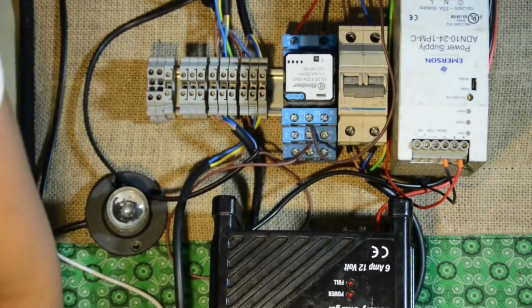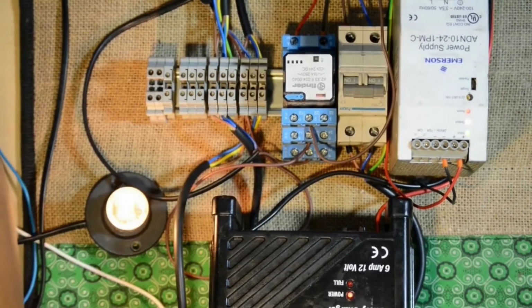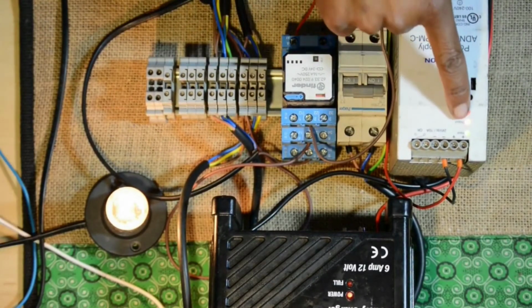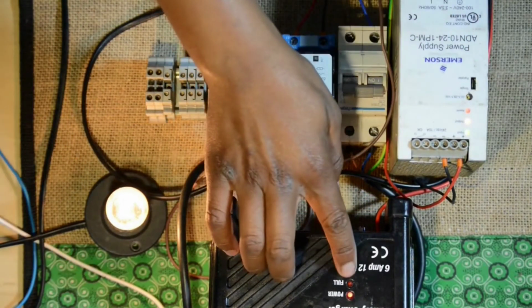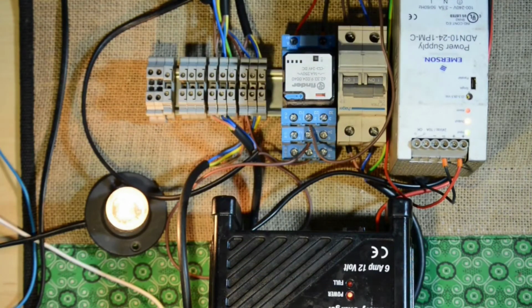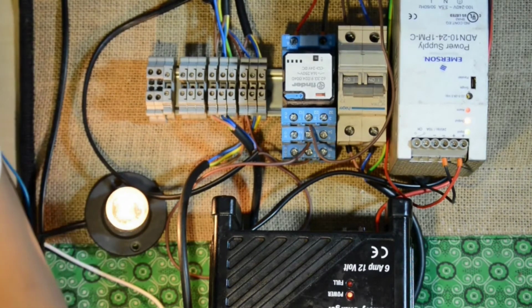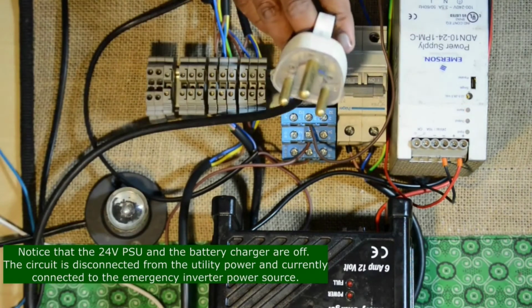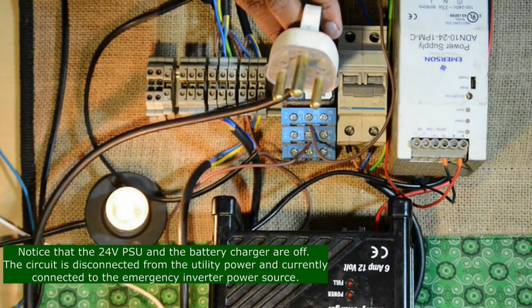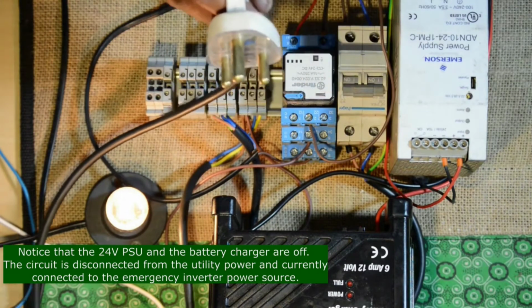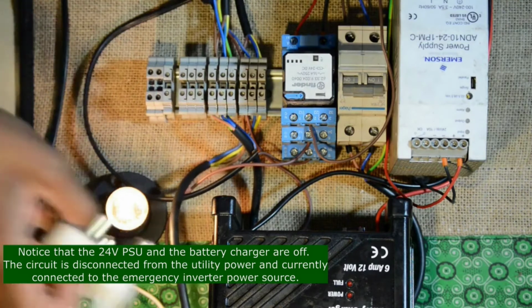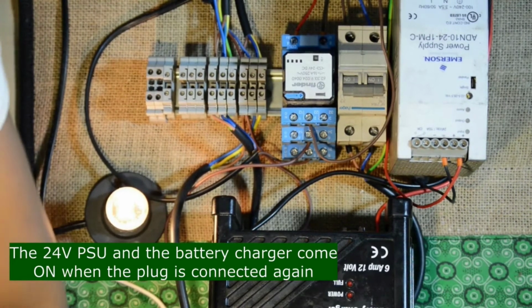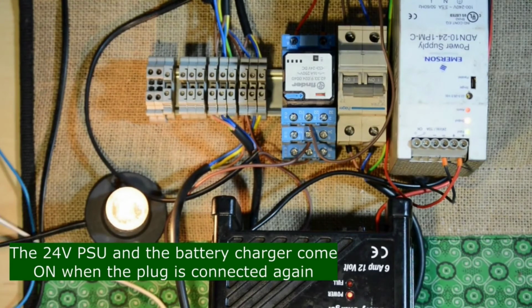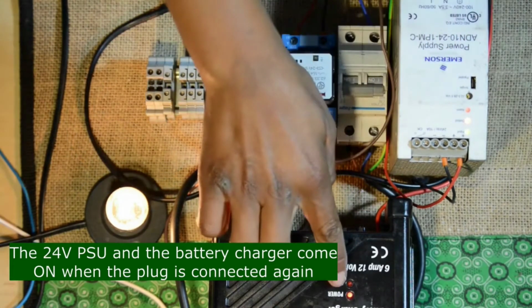So now that we've assembled this, we're gonna go ahead and plug in and see what happens. And as you can see, the light goes on, the power supply goes on, and the light on the charger also goes on. So next, what I'm gonna do is pull out the plug to simulate a load shedding situation. As you can see, all those lights go off, and next our power goes on. There's a bit of a delay there, but as you can see, the lights to the charger and the 24 volt supply are off, and now they're back on.